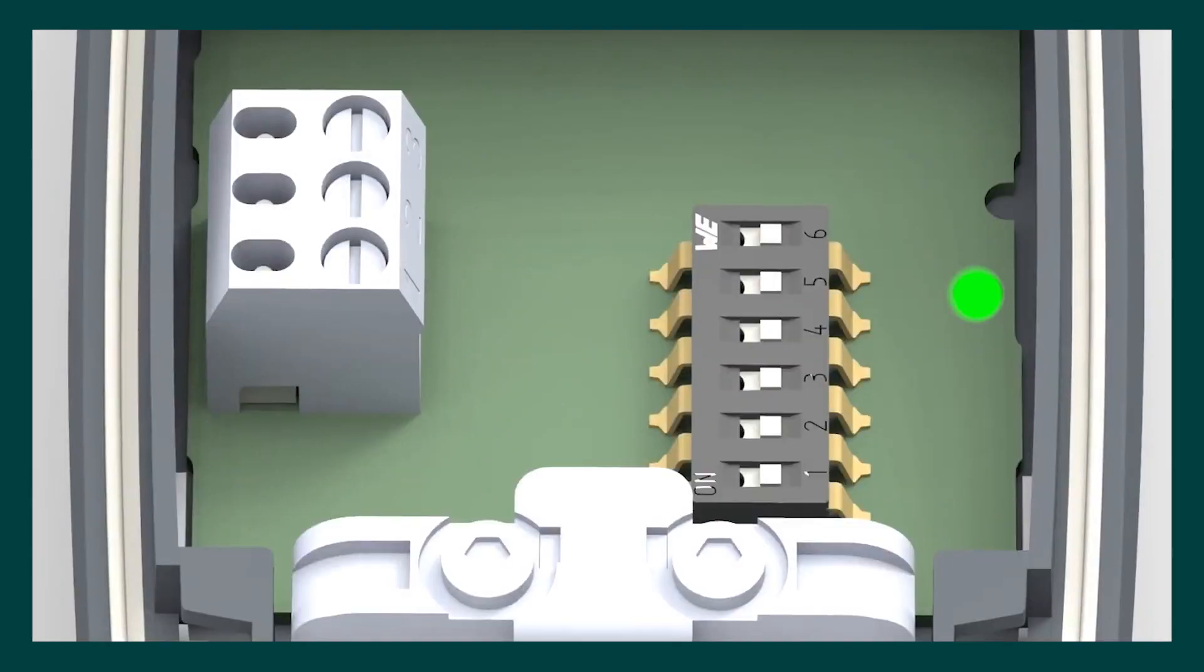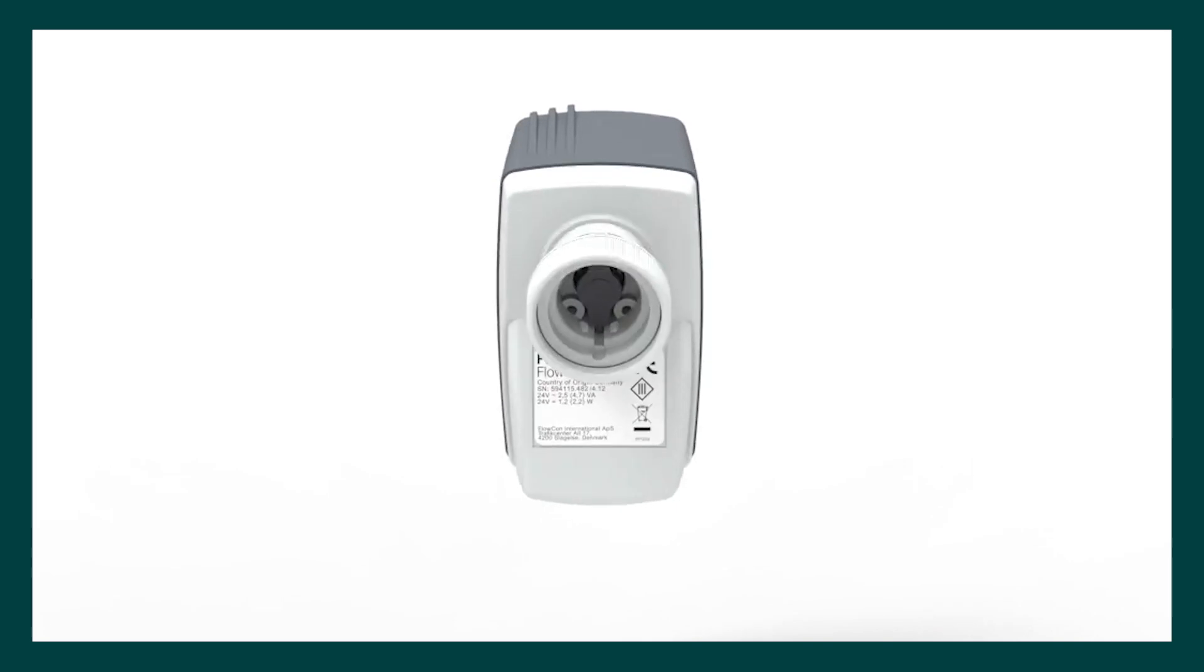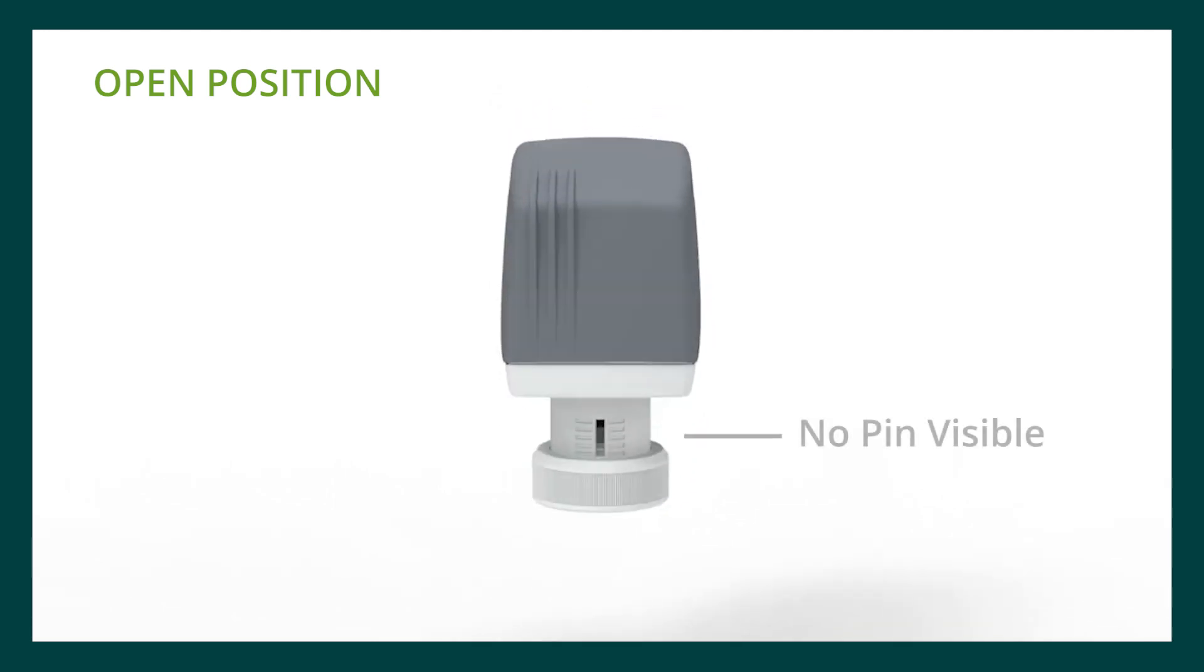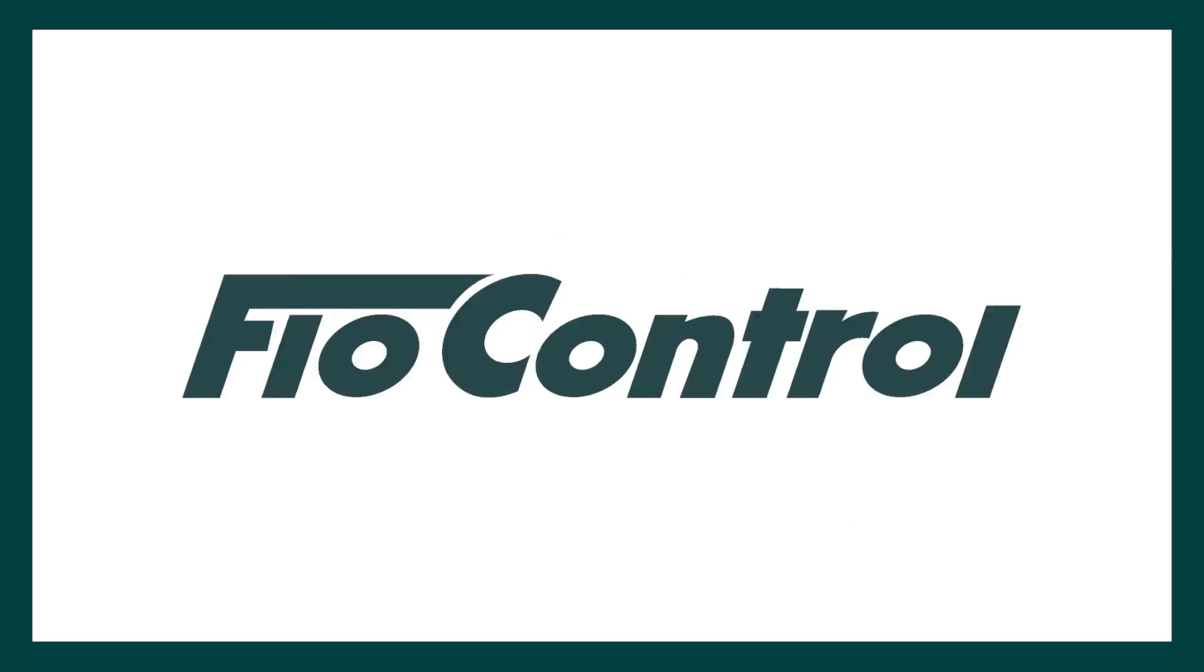Only remove the actuator from the valve in the fully open position. Drive the actuator open with a control signal or flip dip switch 6 to the on position. Once fully open, turn the power off. Dip switch 6 should be reset to the off position and should remain in this position whilst the actuator is not fitted to the PICV. Only remount the actuator onto the PICV in a fully open position. Once remounted, turn the power on. The actuator will recalibrate to the PICV. For software version specific calibration and fault finding tips, please visit the FloControl website.